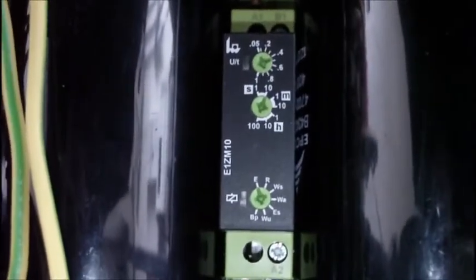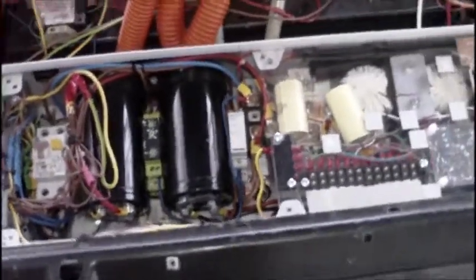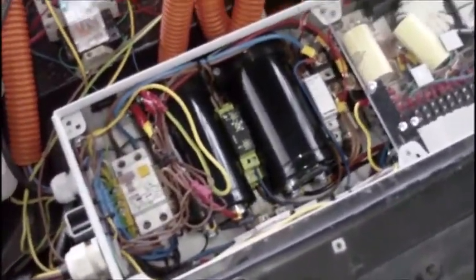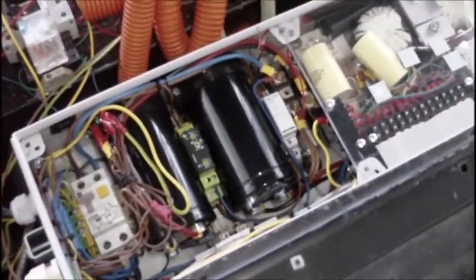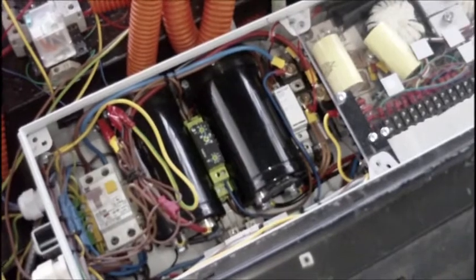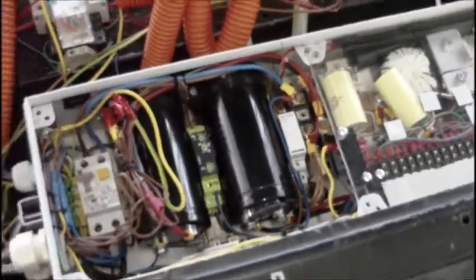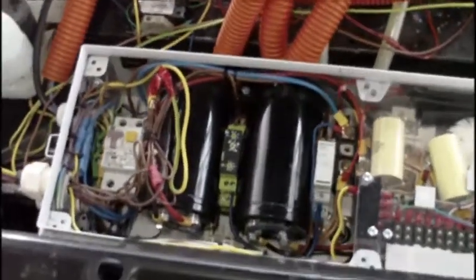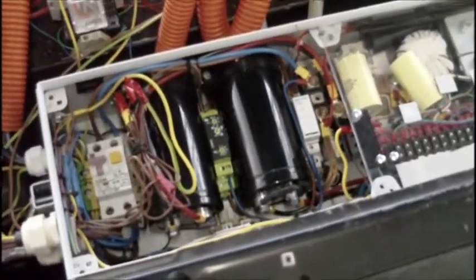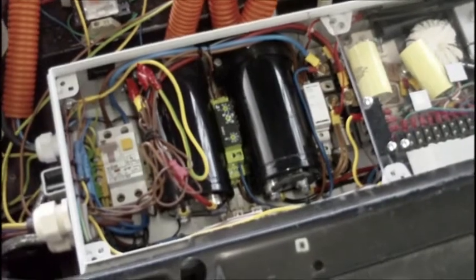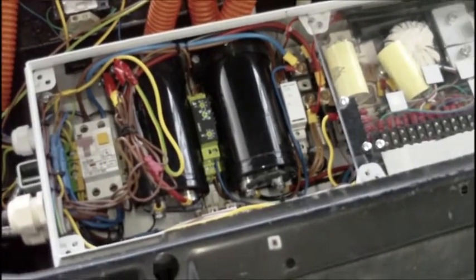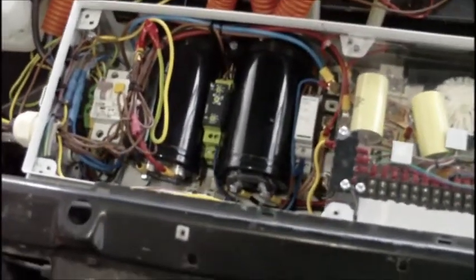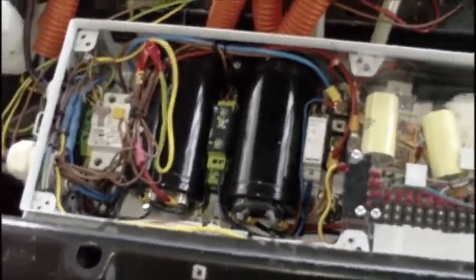And what I've got it set for is on delay, 4 seconds, about 4 and a half seconds. So that when the mains is connected to the charger, it gets a 4 second delay before the contactor closes, and thus allows plenty of time for the capacitor to fully pre-charge to the DC bus voltage before the contactor closes.